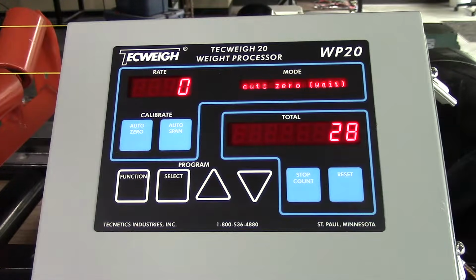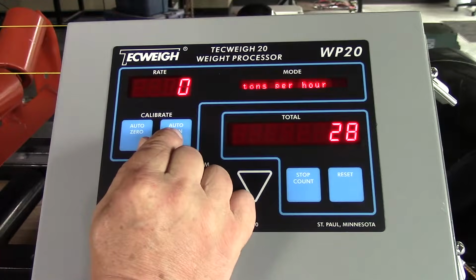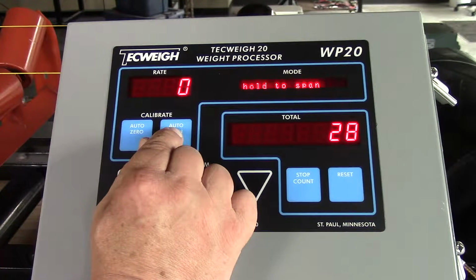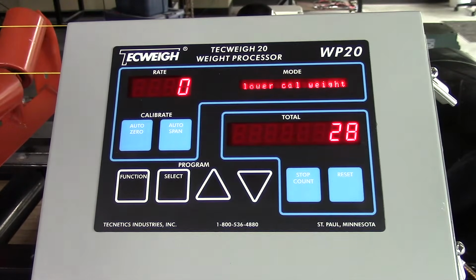In this case it's going to run for 2 belt revolutions, but we have it programmed to calibrate relatively quickly for the sake of this training video. So as soon as 2 belt revolutions are complete, it will come back and say the calibration's finished and go back into tons per hour. The next calibration we would do typically would be a span calibration. And so then we would apply the test weights, or hold it first and then it will say lower cal weights. If you already have the cal weights lowered, then all you need to do is just hit auto span once more to acknowledge that the weights are lowered.